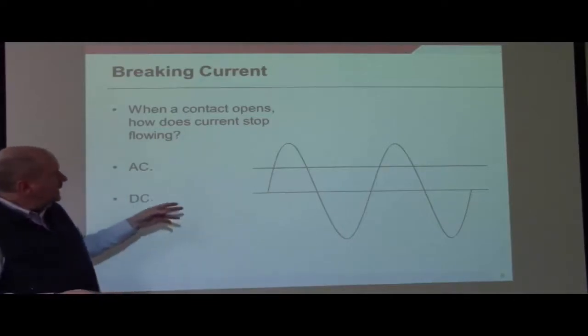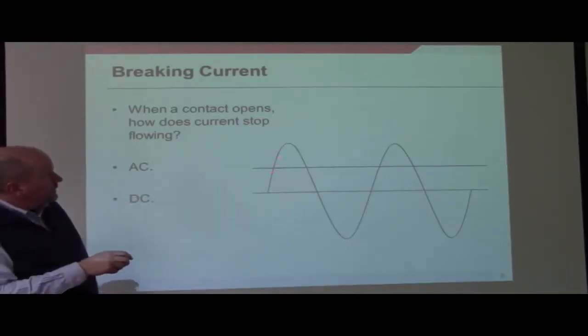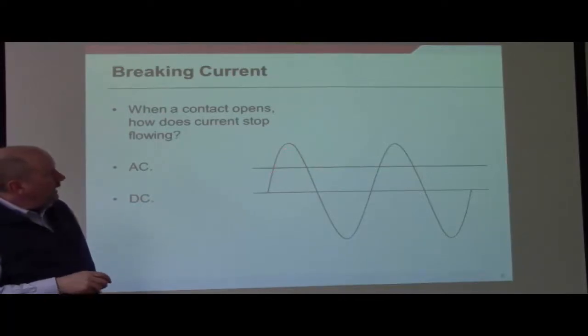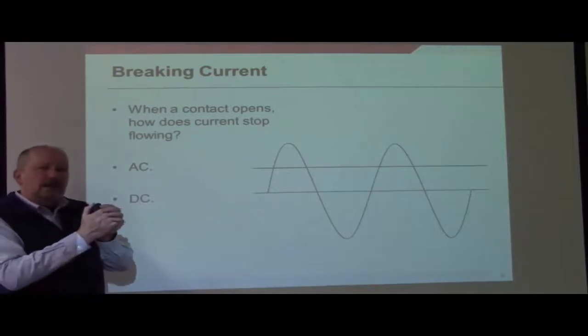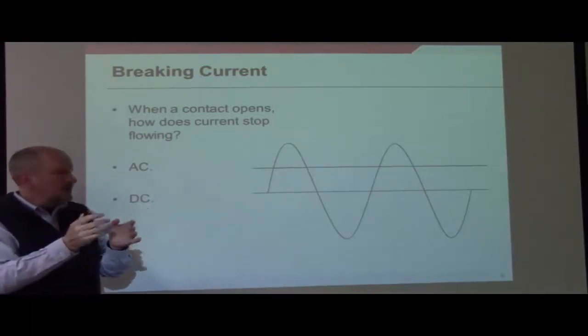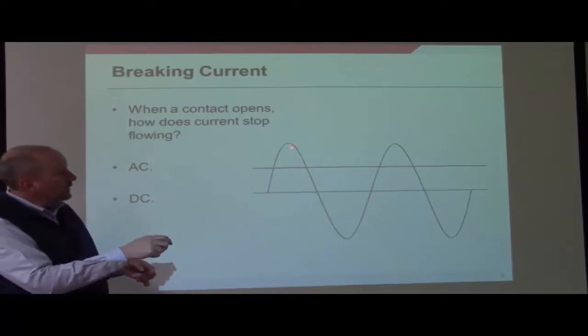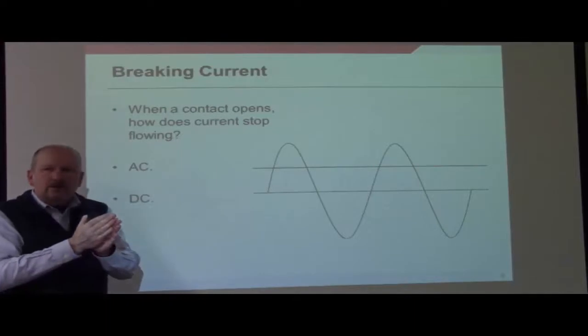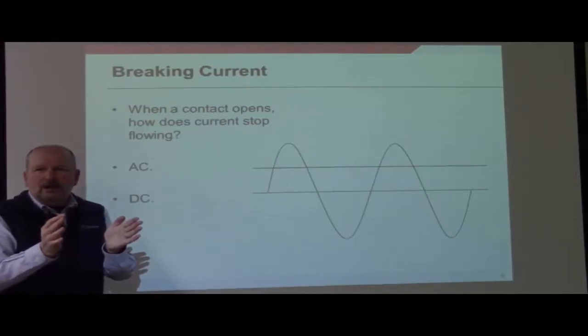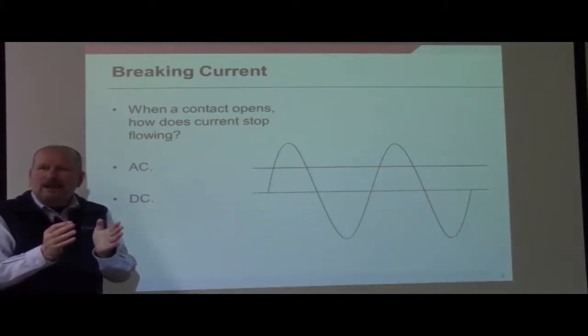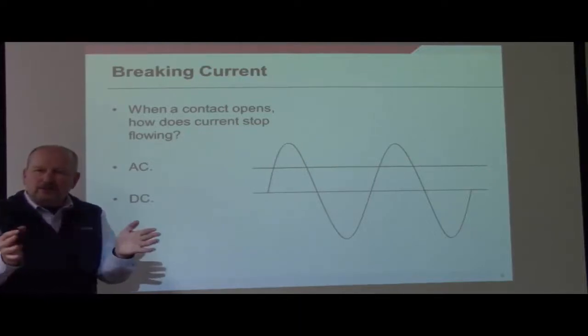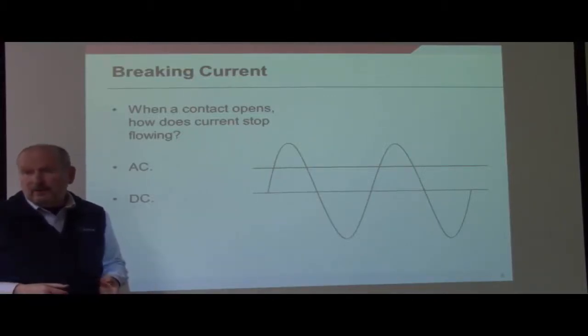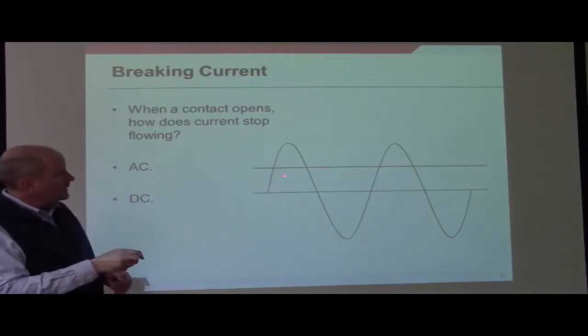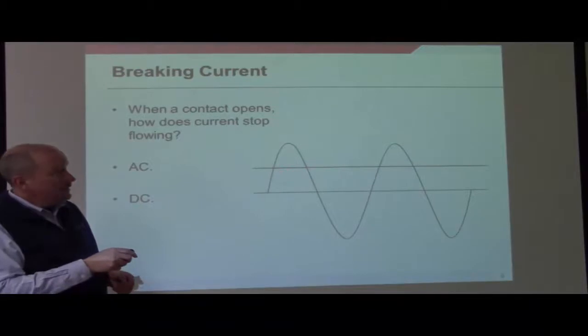Now, in the case of AC, which is this sinusoid shown here, what happens is you'll go to open the contact, the contacts will pull apart, and inevitably they will not be at a current zero. And so as they pull apart, say they start opening somewhere around here, they're going to actually draw a small arc. And then as the voltage goes through zero, that arc will extinguish, and as the voltage then increases between the contacts, that arc simply does not reignite, and you have successfully interrupted the current. However, in the case of DC, which is represented by this line, there is no current zero.